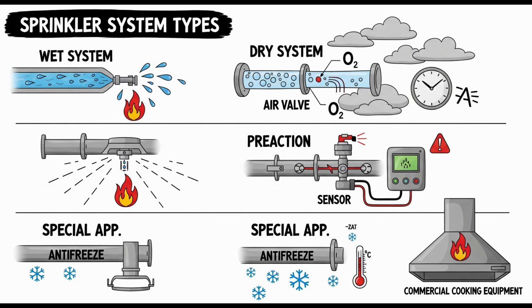The trip pressure is the minimum air pressure needed to hold back the highest normal water pressure, based on the dry pipe valve's specific design ratio, sometimes called its differential. Different valves have different ratios of air pressure needed per psi of water pressure. So it depends on the valve design and the water pressure it's holding back. Correct. So you need enough air pressure to meet that calculated trip point, plus a 20 psi safety buffer to keep the valve securely closed against the water pressure. Okay, air pressure is critical.